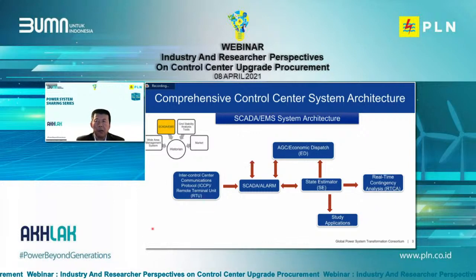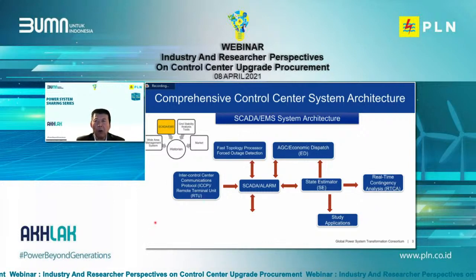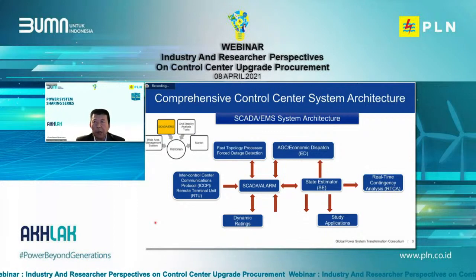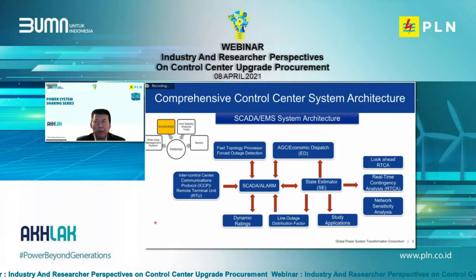Then you can extend your EMS and SCADA to cover more functionality. For example, you can extend with fast topology processor. You can get quick topology results and alarms that tell you how the system changed before you get the state estimator or RTCA telling you what's the real-time violation. Then you can have outage detection, which can tell you if it's really a planned outage or a forced outage.